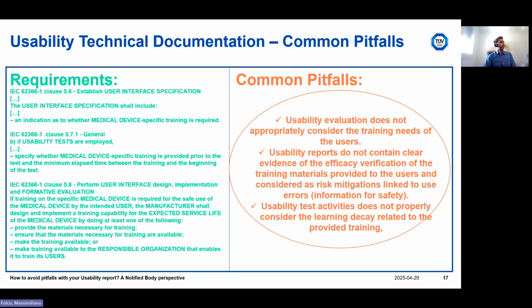And then the standard requires, with clause 5.8, the manufacturer to design training material, so to design and implement a training capability for the expected service life of the medical device. So this means that if the manufacturer has defined that training is needed for the intended users, then training materials shall be developed during the design and development phase, shall be validated, and shall be provided to the users for the expected service life of the medical device.